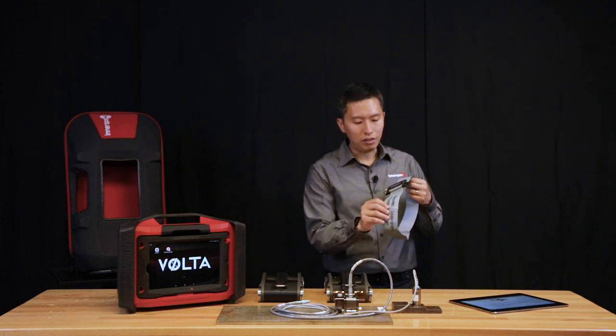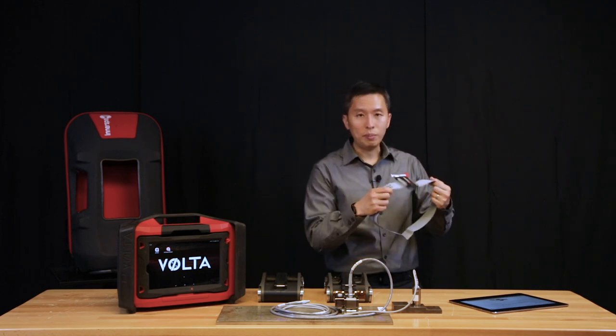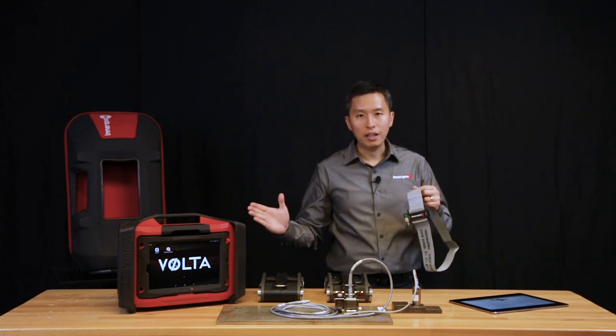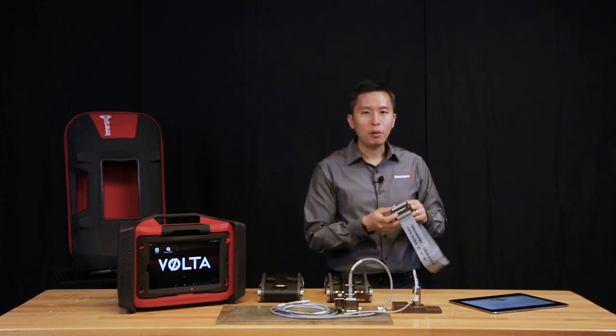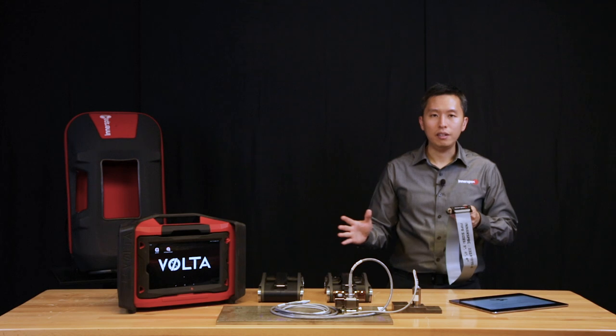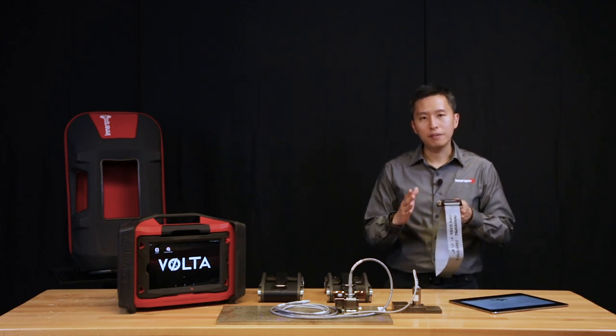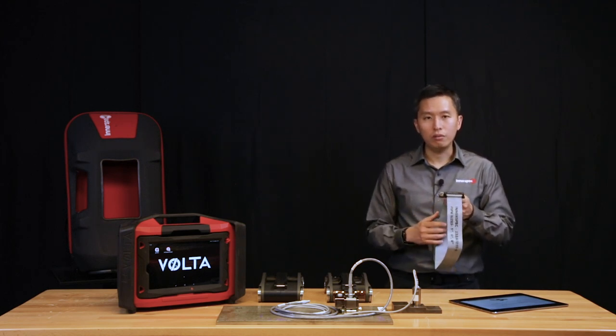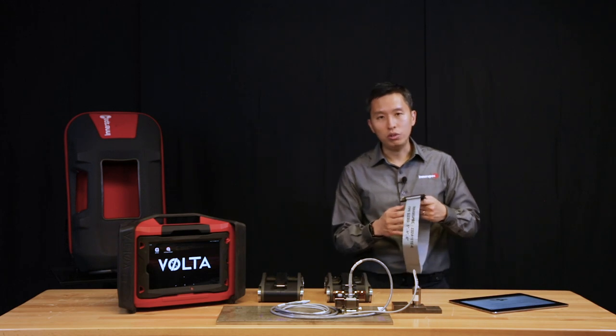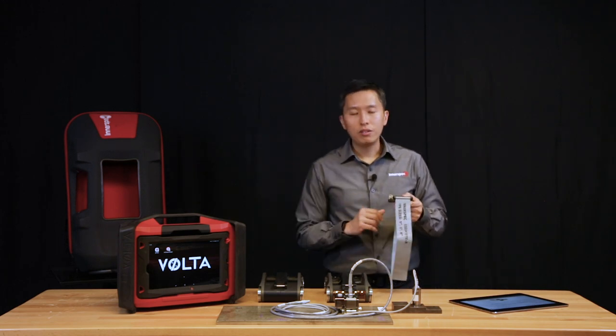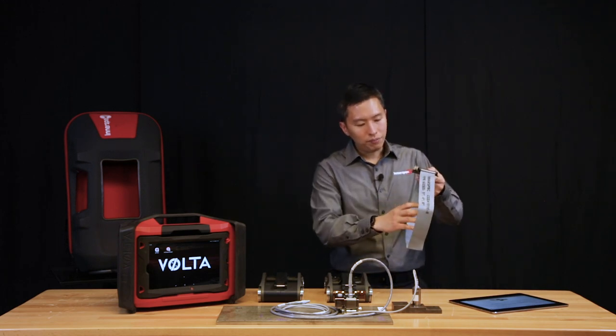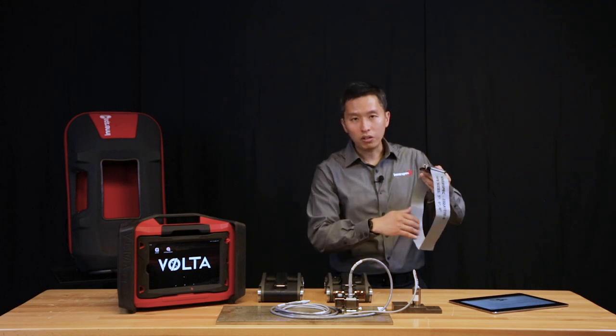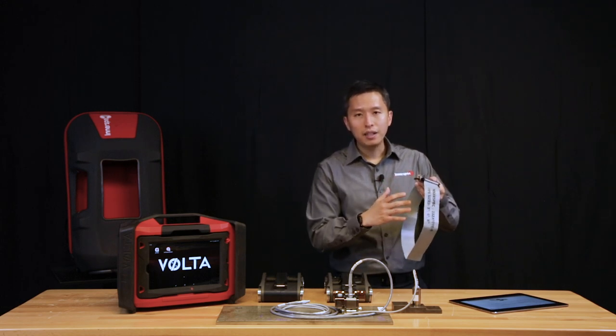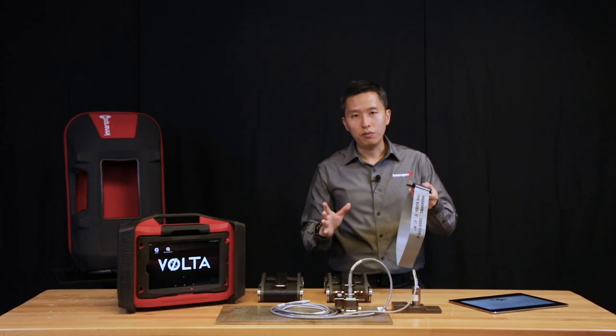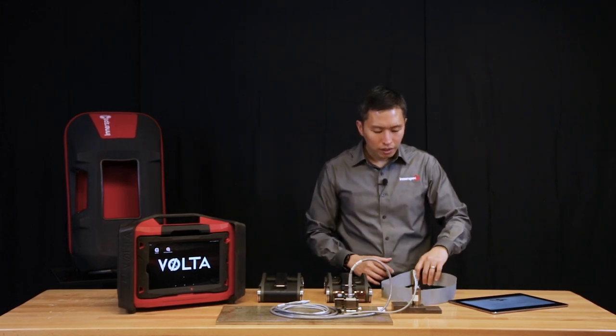So, LRUT axisymmetry inspection. It uses this ribbon collar to transmit sound as well as to receive sound. It provides a pure wave mode and it has very excellent signal to noise ratio as well as good resolution axially. Because the sound is transmitted along the circumference of the pipe, it has no circumferential resolution.